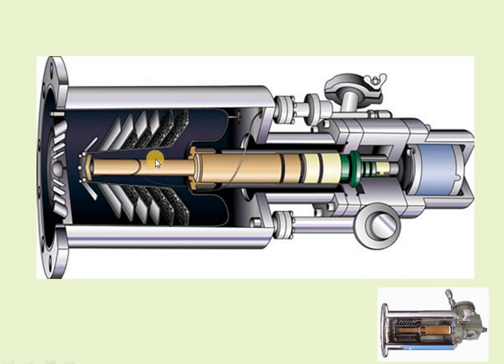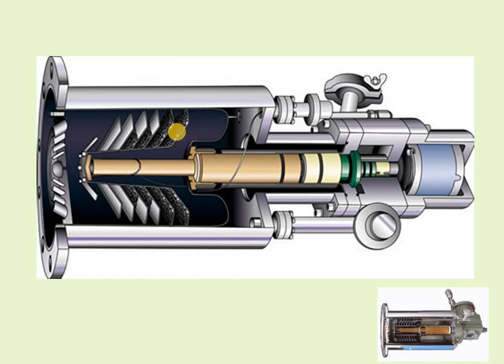There is a metallic tube through which cryogens — liquefied gases — are brought and circulated. A compressor helps circulate the cryogens through these panels. Liquefied cryogens like liquid hydrogen, liquid nitrogen, and liquid helium are circulated, causing the cryopanels to cool down progressively from around 120 Kelvin to around 4 Kelvin.